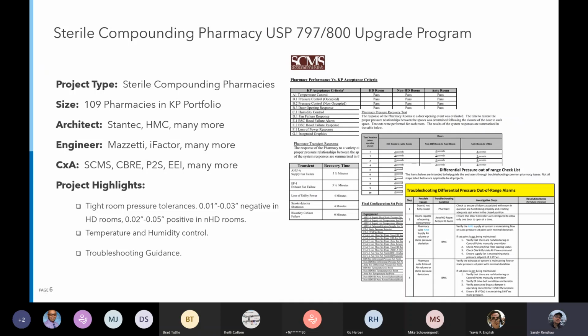The final highlight is the sterile compounding pharmacy USP 797 and 800 upgrade program. The program included 109 pharmacies with the involvement of multiple architects, engineers, and commissioning agents. The tolerances for control were quite tight, especially for room pressure. The highlight here is in the gradual improvement of the process, specifically in the presentation of the final acceptance of the pharmacy in the commissioning report.